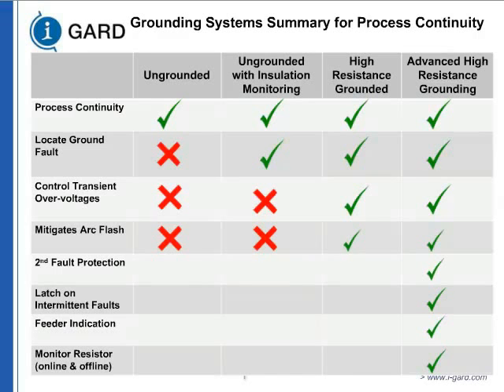So high-resistance grounding gives you overvoltage protection. Otherwise, you see it minimizes arc flash. How does it do that? High-resistance grounding is the only one to do that because the first fault is going to be less than 5 amps. You do not have any arcing in there. You can detect it. If you have a second fault protection system, you can detect it and remove it. Would it reduce the incident energy? Absolutely not. Would it reduce the risk of arc flash? Absolutely yes. Then you have the capability to latch on intermittent faults. You don't have people. People are becoming a very priceless commodity you can't afford. You can have a feeder indication that tells you which feeder it is. If you are concerned about resistor monitoring, so that you don't take routine outages, you can have online monitoring. So you can build your system based on what you need.